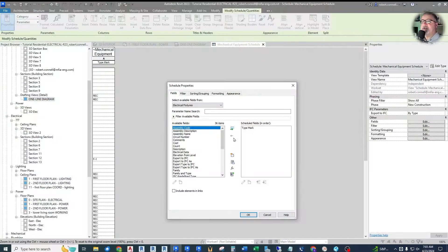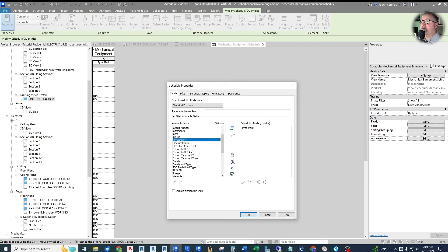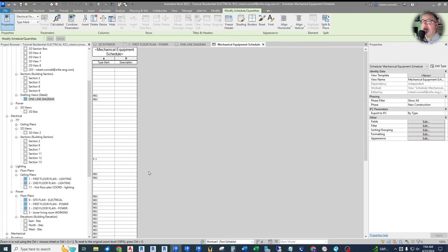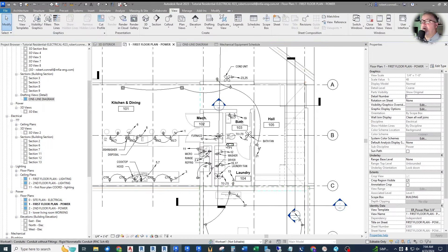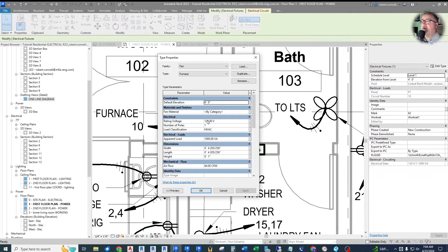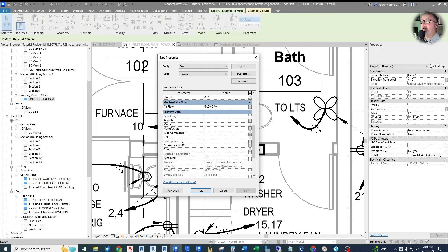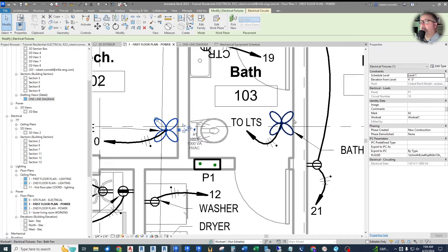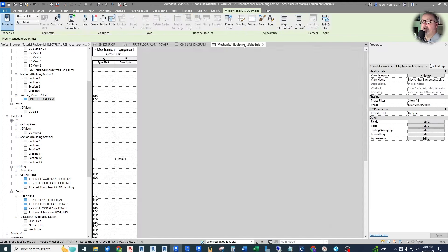The next field I like to show is a Description to explain what F1 means. Let's go down and find the description parameter in our fixture and bring that into our schedule. Now we have another column. We can go into our pieces of equipment and start typing in a description — go to Edit Type and find the Description field. For the furnace, type 'FURNACE' — I use all caps. Now, because we have a schedule, the data is bi-directional: it comes from the database but also feeds the database, populating all instances of that type.